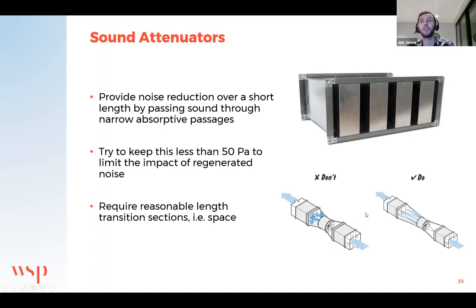The data that is provided, including pressure drop data, is all based on what would be called typical installation scenarios, but this is basically where the attenuator is open to a laminar flow of air in essentially a straight duct with no obstacles in the way.